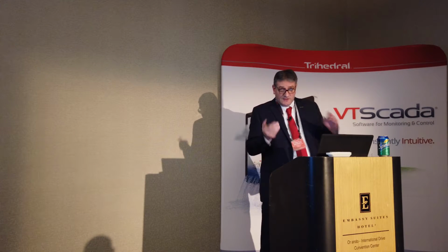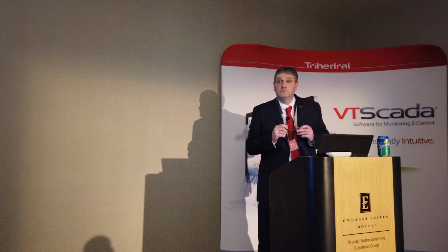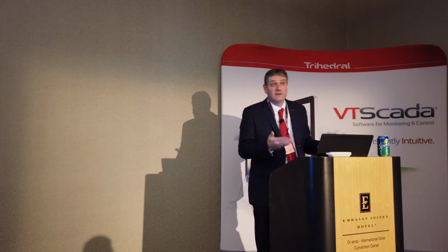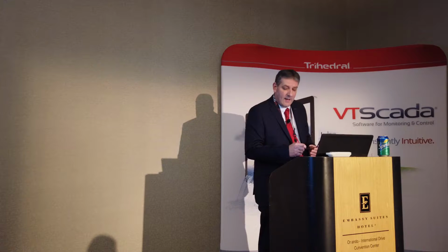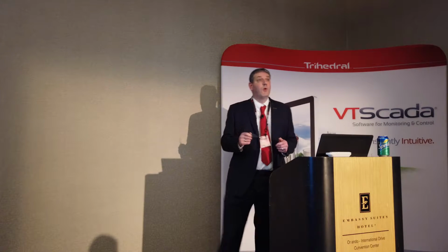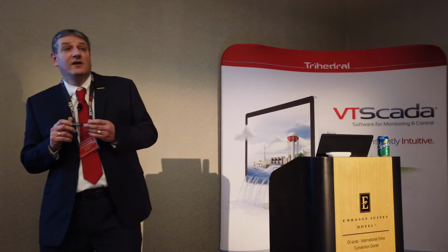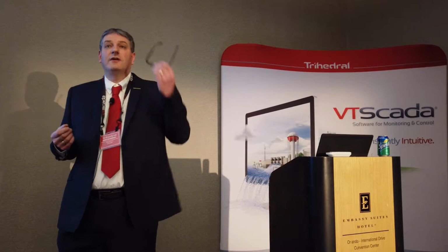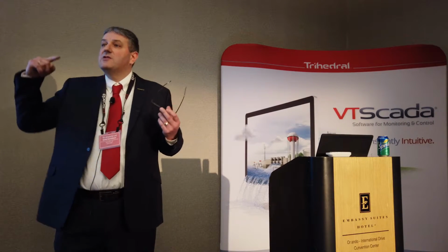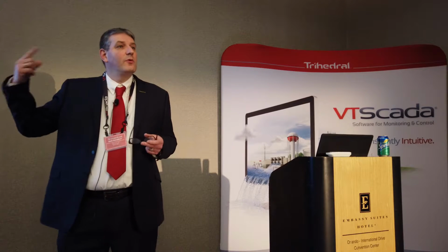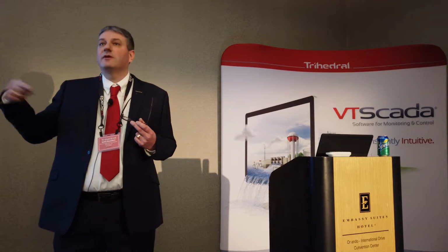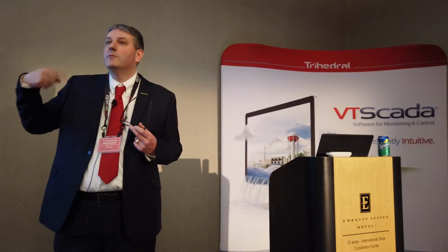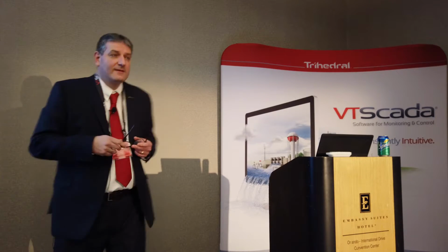So where does this become useful? Well, it's kind of interesting, but where does it become useful? I'm sure you've all heard of the if-one condition. Again, I spoke about it at the script course. This is a condition in VTScada where you do if true, and you get caught in an execution loop where VTScada is just simply burning the CPU, executing around that loop just as fast as it can.